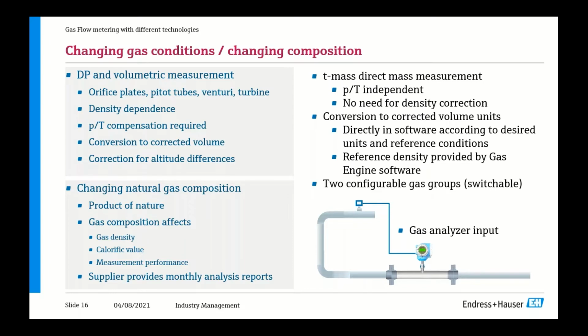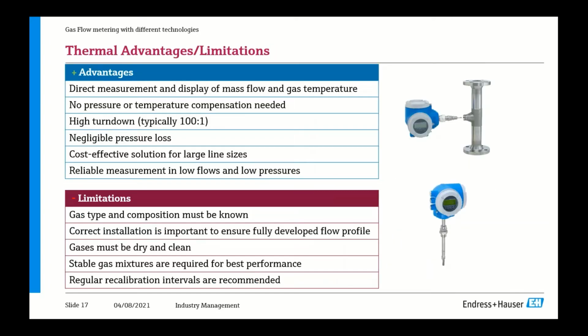Next slide, please. To summarize very quickly, there are a number of benefits with the T-mass, with thermal mass. It is a direct mass measurement, as I mentioned. It has a very large turndown with very little pressure drop. It can be used in low to very high flows and also in very low pressures. Some of the disadvantages are, of course, that the gas composition must be known. Due to that, we do recommend a stable gas mixture. Also, the installation is important because it does need a fully developed flow profile, and the gases should be dry and clean. And with that, I would like to turn it over to Erwin.